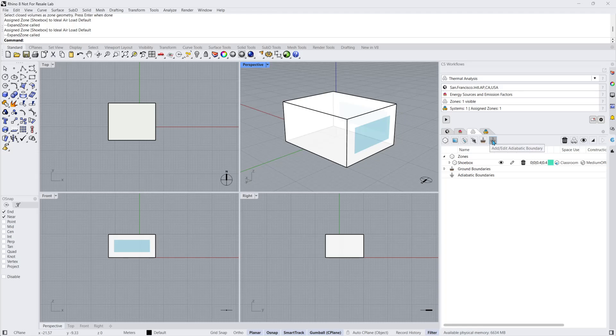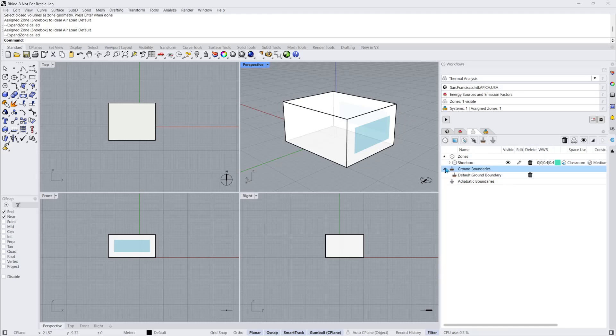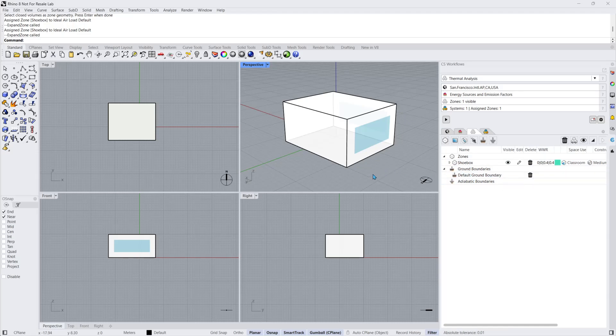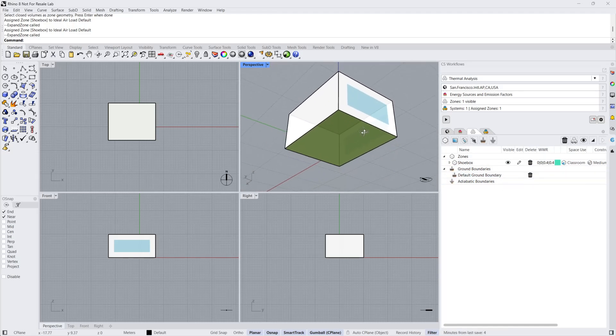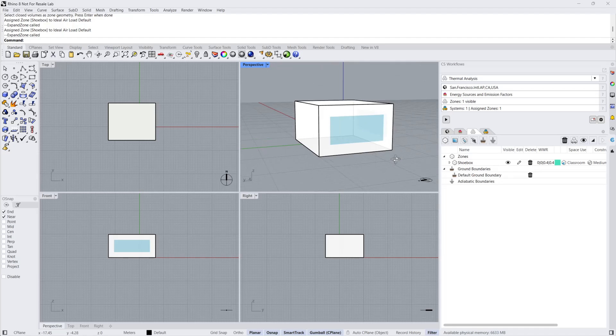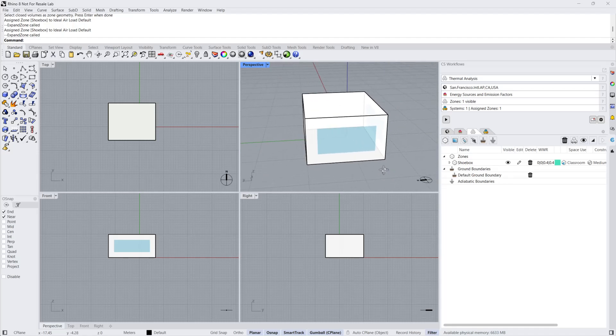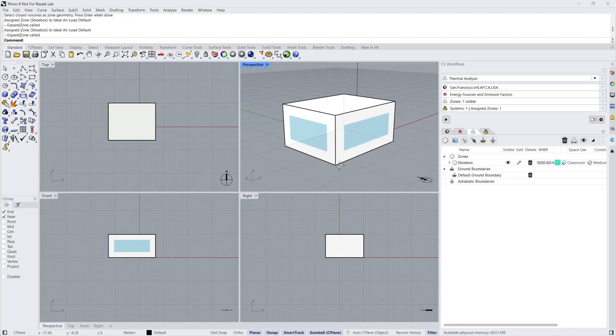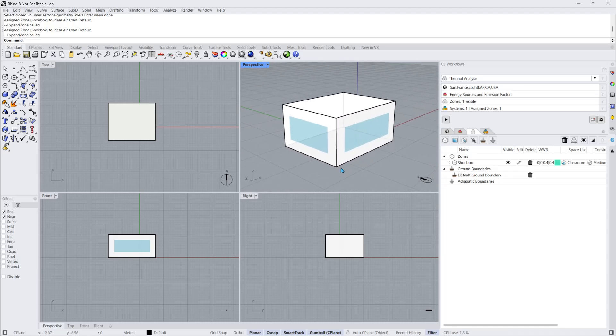Boundary conditions are surfaces such as interior adiabatic surfaces or the ground. A default ground is provided for any new thermal model where Z is zero. Ground surfaces are colored green, as you can see here. Nearly every thermal model needs ground surfaces. Otherwise, the building conceptually floats above the ground, and the floor surface is exposed to the outside air.